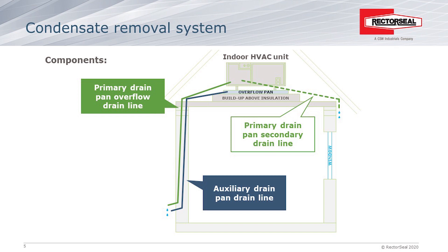Float switches are also used in the primary drain line for the same purpose. These air handlers and evaporator coils are located in closets, garages, or horizontally in an attic, and they all require in most places a secondary safety pan underneath the whole unit. In case the primary drain pan clogs and the float switch is not installed, that water is going to overflow and we want it caught in a secondary pan, which will also have a float switch for extra protection.